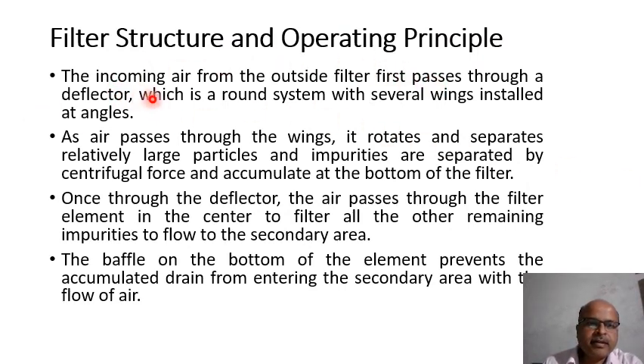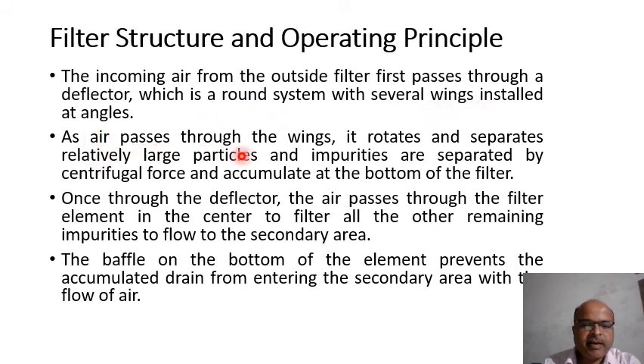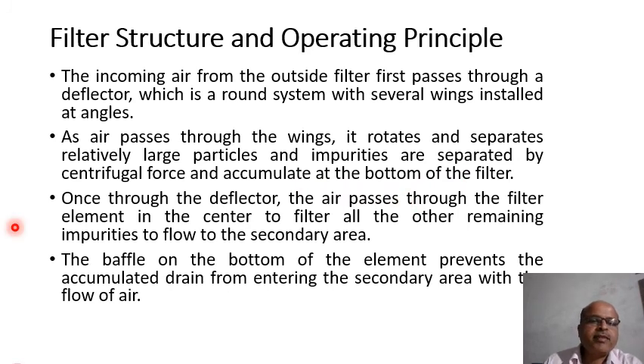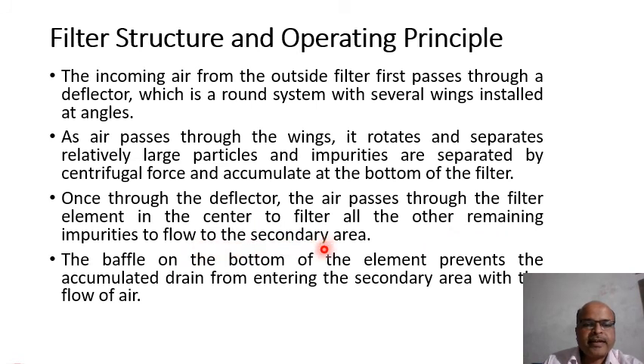Filter structure and operating principle: The incoming air first passes through a deflector, which is a round system with several wings installed at an angle. As the air passes through the wings it rotates, separating relatively large particles by centrifugal force, which accumulate at the bottom. The air then passes through the filter element in the center, and the baffle at the bottom prevents accumulated drain from entering the secondary area with the flow of air.